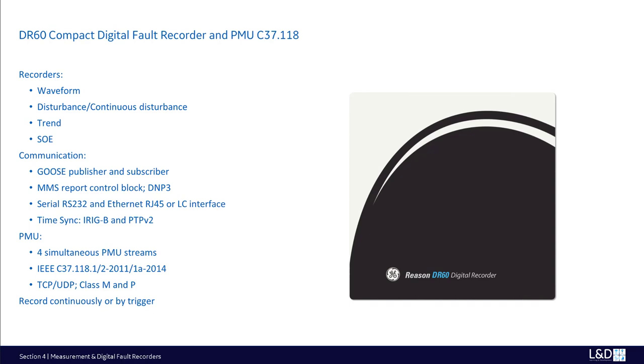Born with IEC 61850 spirit, all the DR60 internal functions are implemented and mapped according to IEC 61850 Edition 2 logic nodes and data models. Even its configuration is performed using the native SCL files. It features MMS report control blocks for communication with supervisory system and Goose publisher and subscriber for interaction with other IEDs through the IEC 61850 process bus. There are serial and Ethernet interface ports with the time synchronized through IRIG-B or PTP v2.